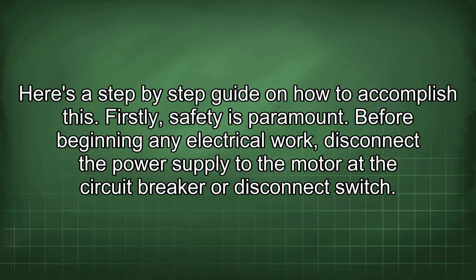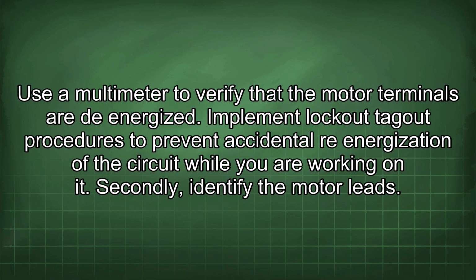Here's a step-by-step guide on how to accomplish this. Firstly, safety is paramount. Before beginning any electrical work, disconnect the power supply to the motor at the circuit breaker or disconnect switch. Use a multimeter to verify that the motor terminals are de-energized. Implement lockout-tagout procedures to prevent accidental re-energization of the circuit while you're working on it.